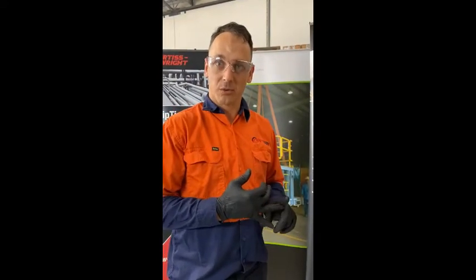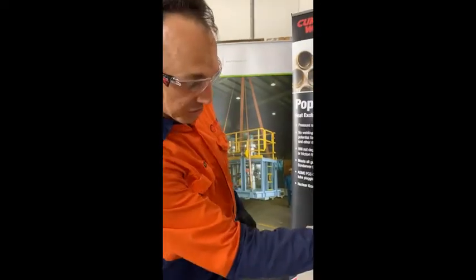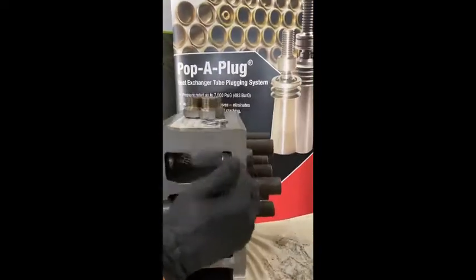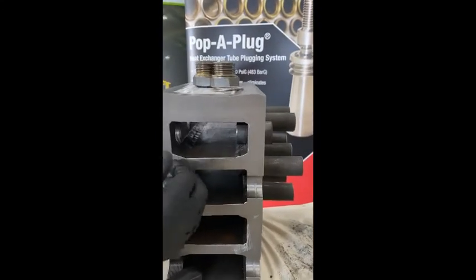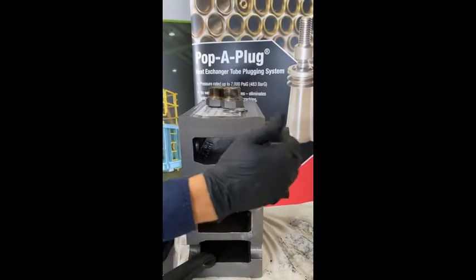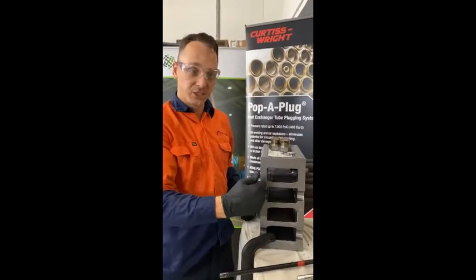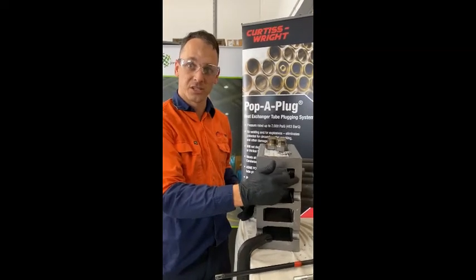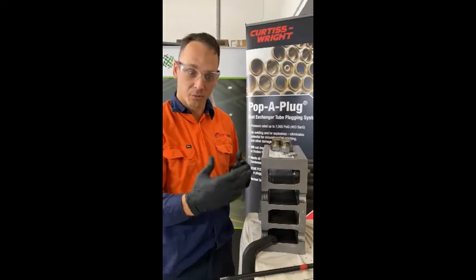We're plugging a tube that's either leaking or being identified with significant wall loss and installing an engineered pop-a-plug into the tube sheet on both sides to take that tube out of action. Part of ASME's recommendations is to puncture the tube or completely cut it off to allow for venting and no pressure build-up behind the plug, as well as validation of the plug once it's been installed so there's no leak path past the plug from pitting, debris, or corrosion.